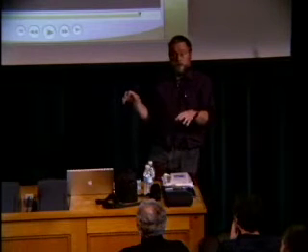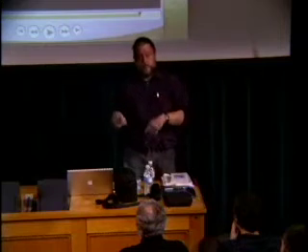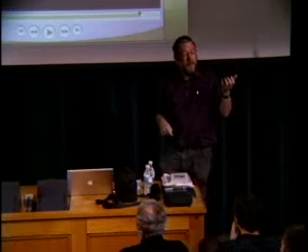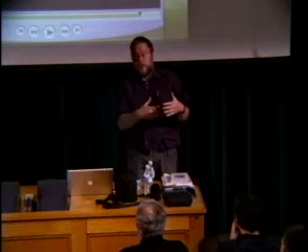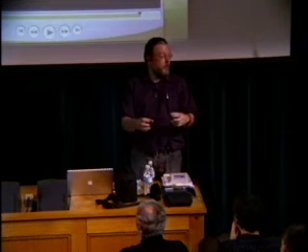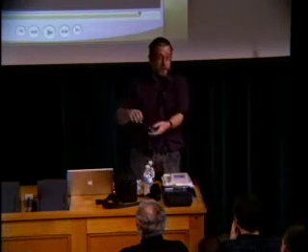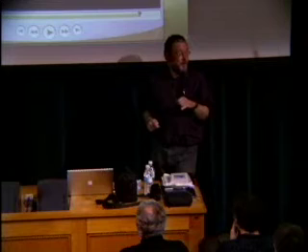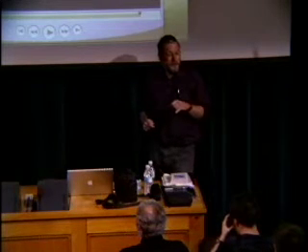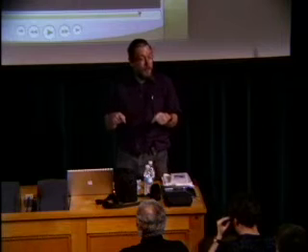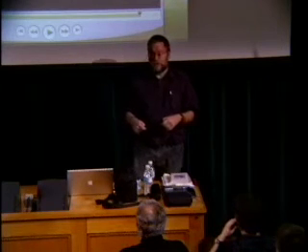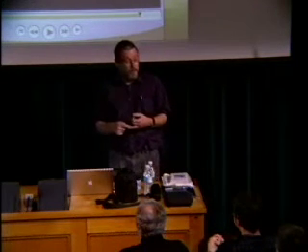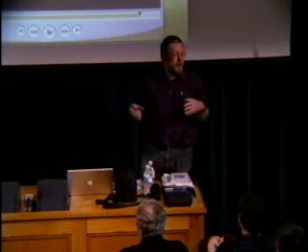So halfway through this 4-hour operation, we've run out of Diprivan, and this is my syringe pump here complaining I haven't used it. The syringe pump has run out of stuff, and a runner has gone to get a new syringe of Diprivan. You pull the old one out, put the new one in, you purge it, and you carry on. Except when he pressed the purge button, he got stuck. And he couldn't get it out of the purge mode back into carrying on. So he switched it off and on again. What does that do? That means you then have to re-enter the patient's weight, and it means the syringe pump has thrown away its metabolic model, or whatever those things are called.